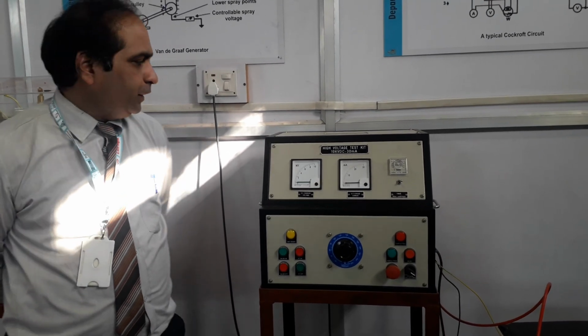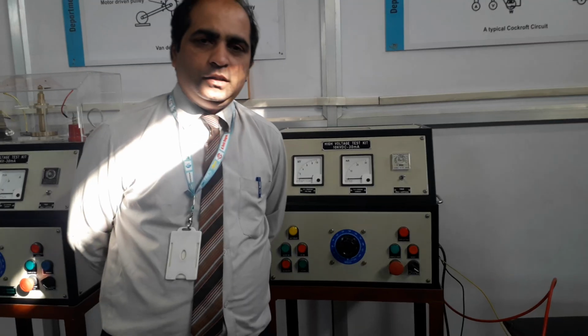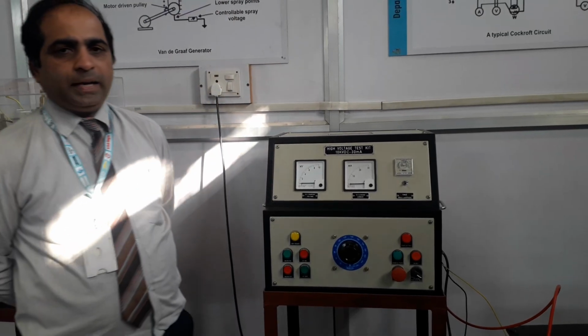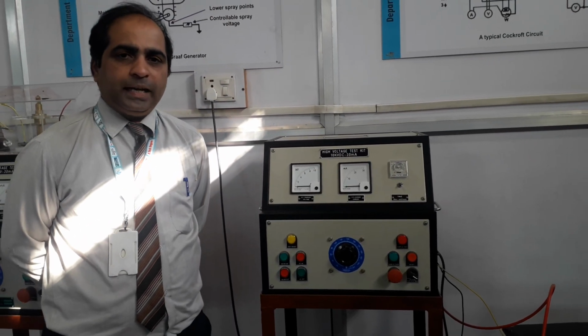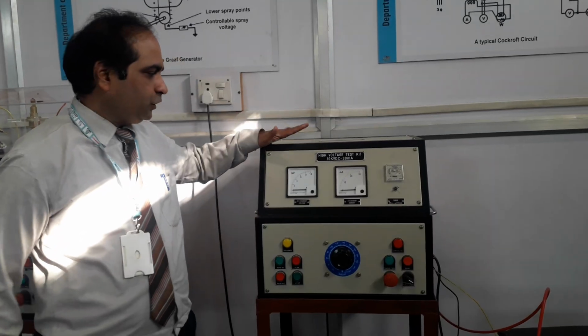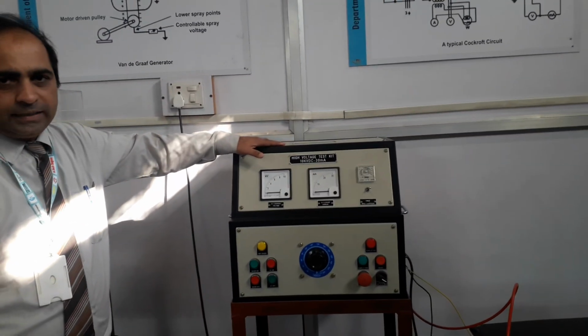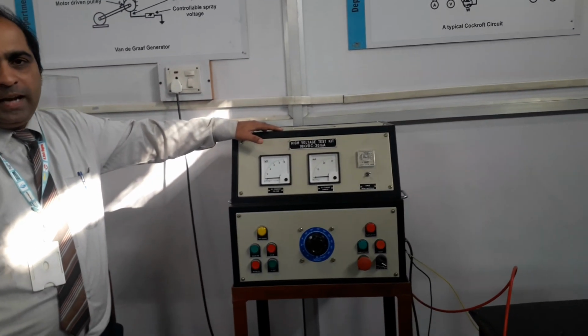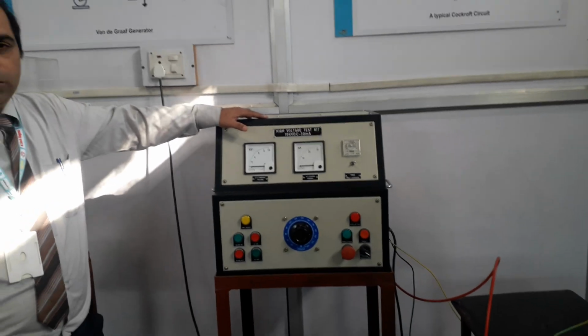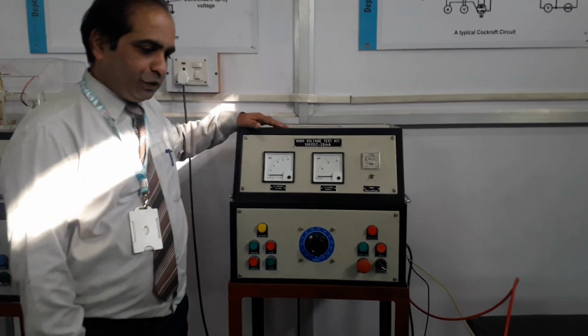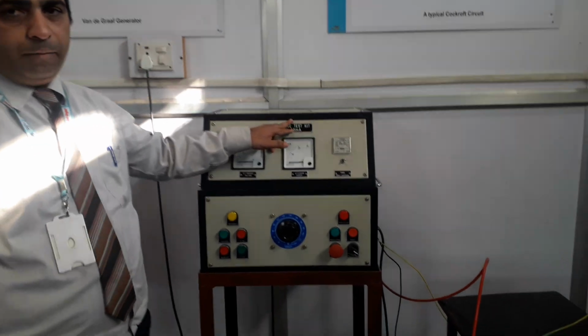Today, we are going to do the experiment on armored cable, wherein you are applying high voltage DC up to 10 kilovolts. The range setting of this particular test setup is around 10 kilovolts, and the maximum leakage current that can flow through the dielectric medium or the insulation medium can be 30 milliamperes.